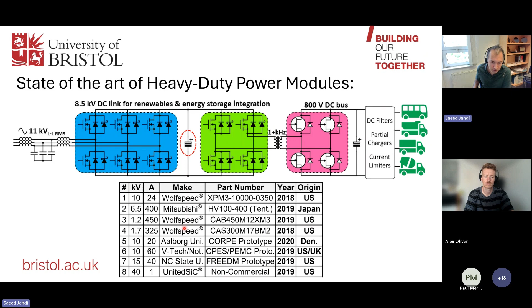That means you will have a first stage of active rectification with silicon carbide MOSFETs, then a second stage of inversion back to AC, increasing the frequency to 1 kilohertz, then active rectification again connected to 800 volt DC buses, and even a 1000 volt DC bus connected to the battery. To enable this, multiple power modules are produced commercially and in research environments around the world.